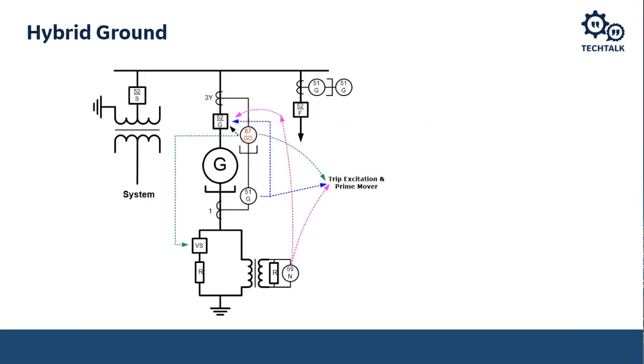The other type of grounding method is the hybrid grounding, and it's a combination of low impedance and high impedance ground methodology. So here, normally when the generator is operating, this switch, a high-speed switch, is closed. So normally we have that low impedance ground in service, that resistor in service that's rated properly for the engineered ground fault current.